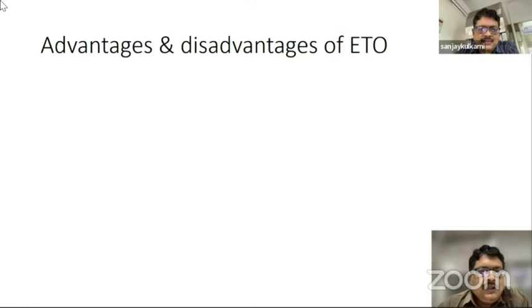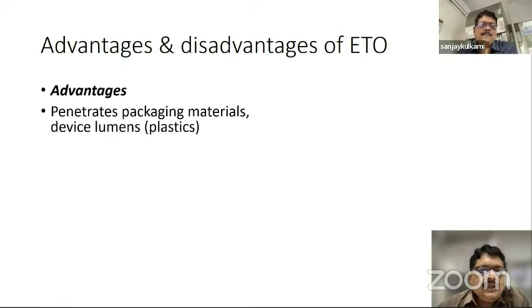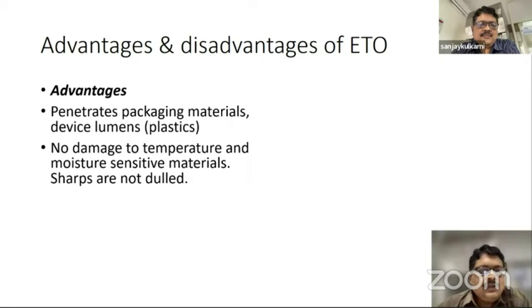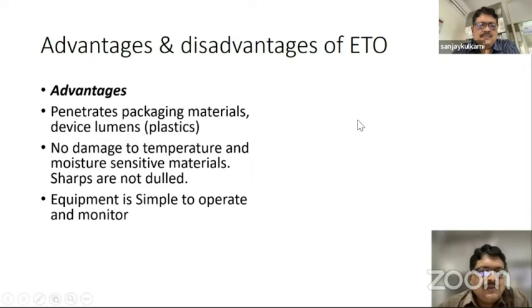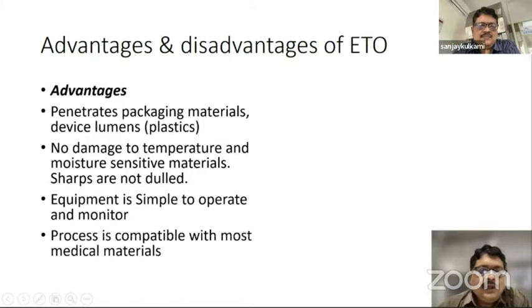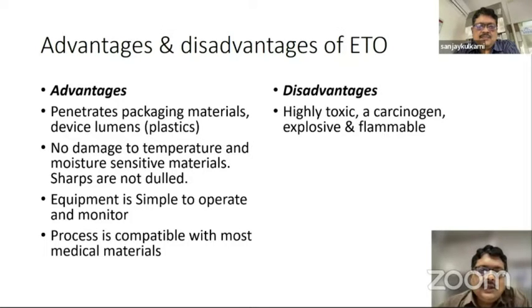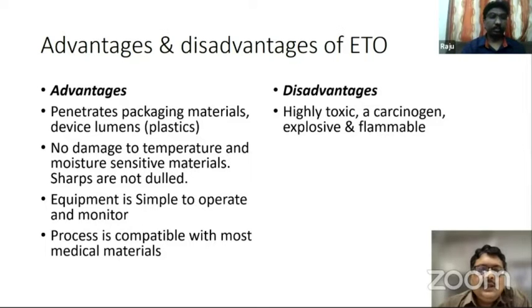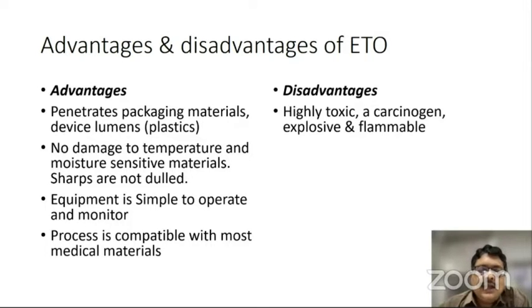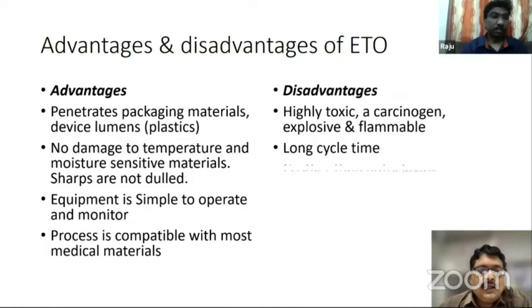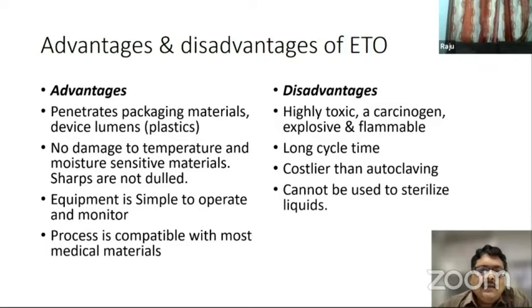ETO has very good penetrating power across various packaging materials and into device lumens, especially plastic devices such as tubings. It does not damage temperature and moisture-sensitive materials. The equipment is also simple to operate and monitor, and the process is compatible with almost all types of medical materials. Among the disadvantages, it is highly toxic, carcinogenic, and flammable, so adequate precautions must be taken. It also has a long cycle time, is more costly than autoclaving, and cannot be used to sterilize liquids.